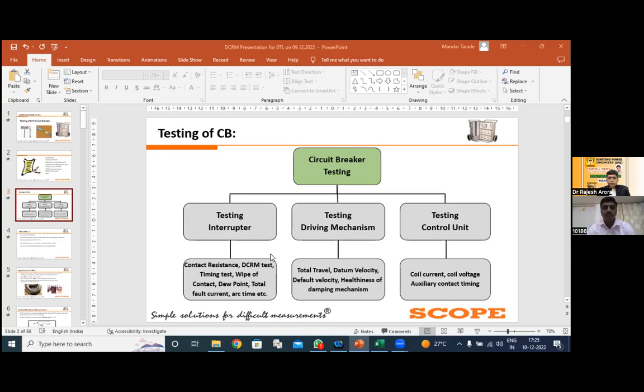Next test is the wipe of the contact. With the help of the travel traces and timing references, we can get the wipe of the contacts. The next one is the dew point, the standard dew point. That means we are using sulfur hexafluoride as an arc quenching medium, so the dew point plays a significant role. As per the standard, the dew point value must be in the range of -60°C to -6. The next one is the fault current, arc time, etc.